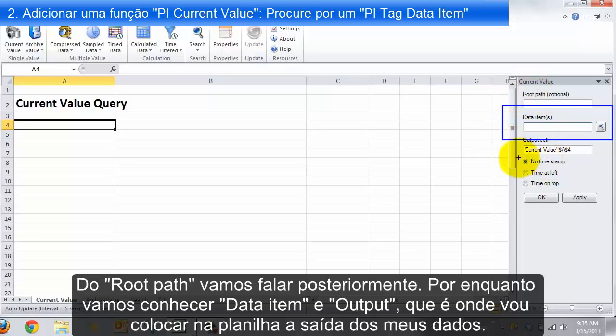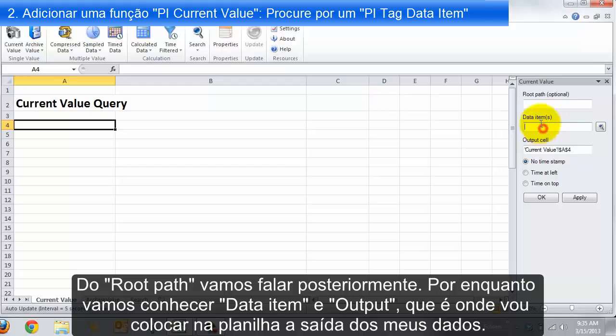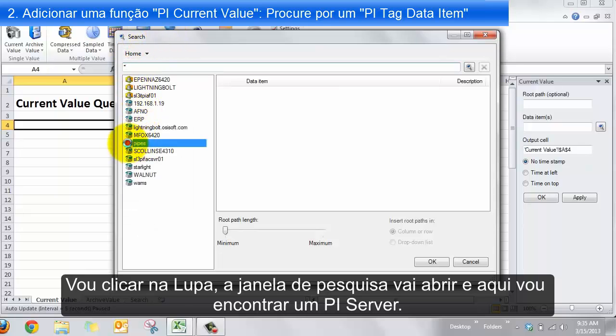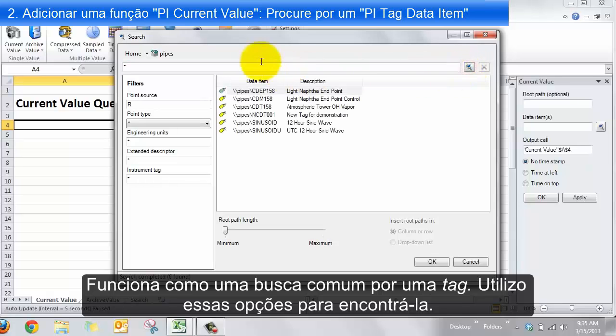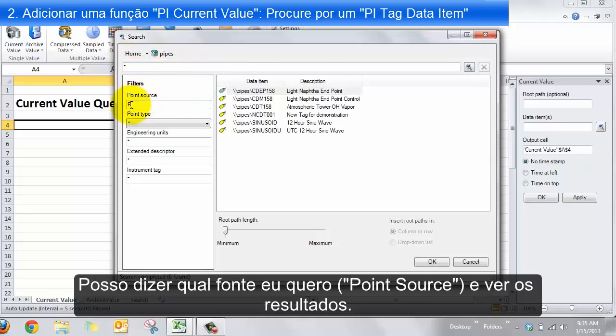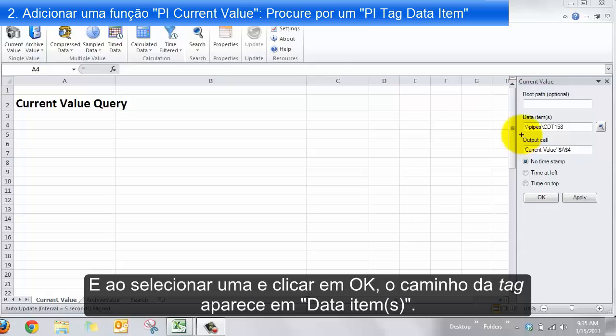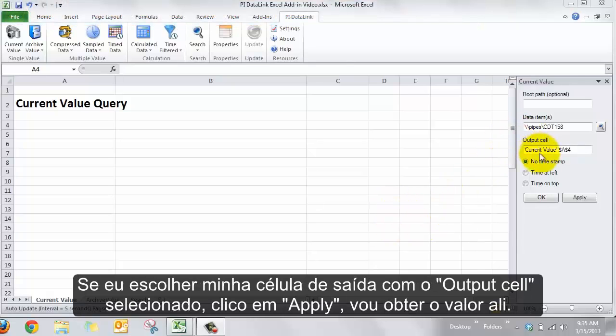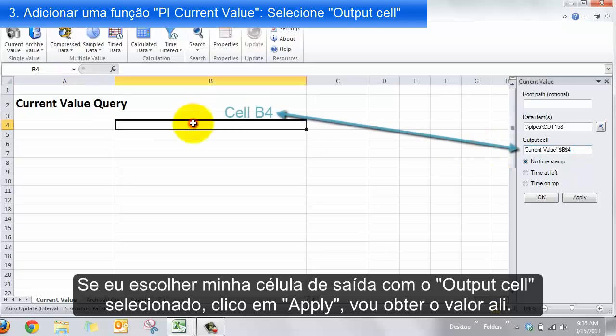We also need to know the output cell — that's where on the sheet I'm going to put my actual output. For the data item, I'm going to click search, and I'll be brought into the search pane where I can find a PI server. If I'm doing a classic search for a PI tag, I can find it just like searching any classic PI server. I can specify the point source, get results back, select one, and say OK — it's put into the data item right there. Then I choose where I want my output to go and say Apply, and I'll get that value.